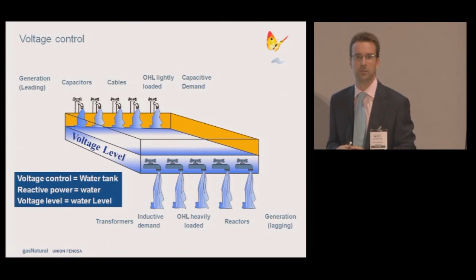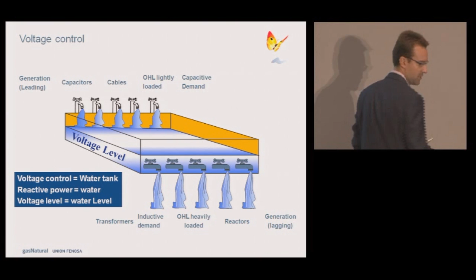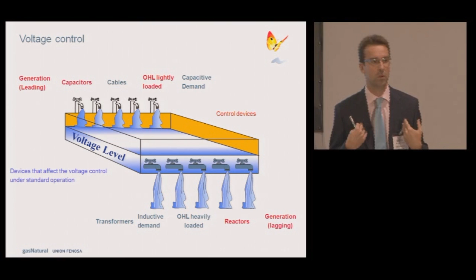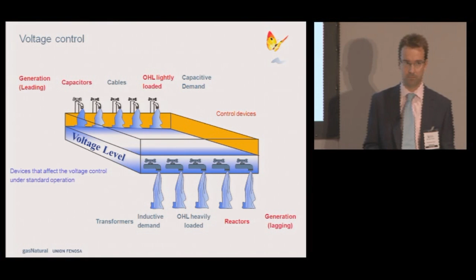We also have some taps that are drains, taking reactive power out of the tank. Among all these elements, some are control devices that we can operate to modify the injection or absorption of reactive power. Others we can't control, but we need to know what they're doing because they affect voltage control.